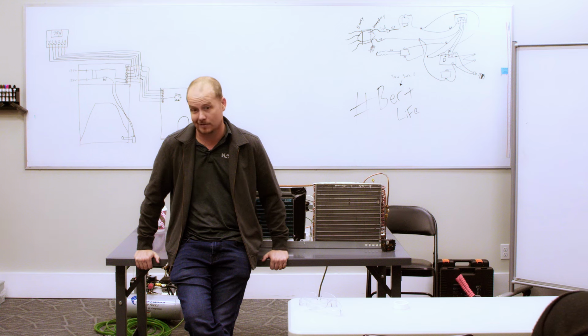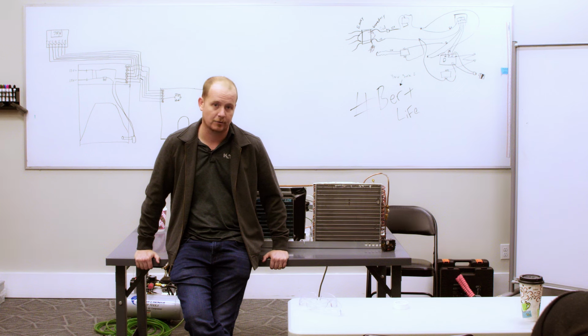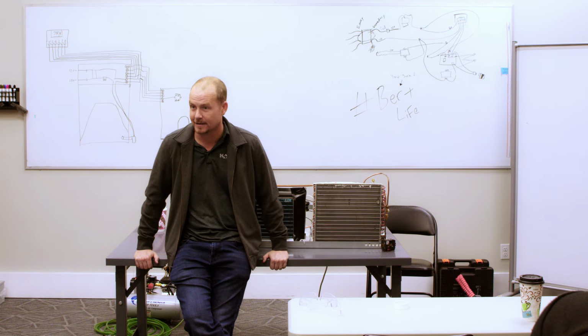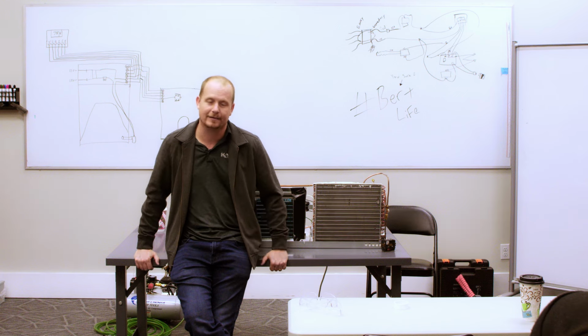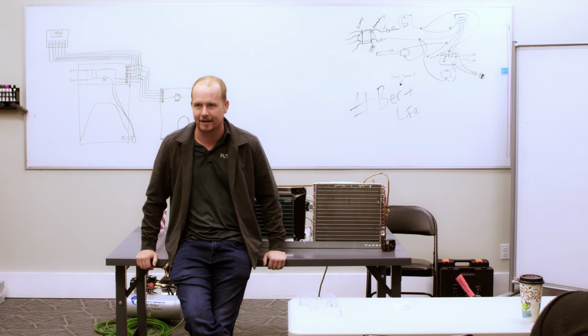And even easier than that, it's almost always around 10. For most of the equipment we work on, other than microchannel condensers, it's so close to 10 that you can pretty much just guess it's 10 in most cases. It may be 8, it may be 14. I'm not telling you not to follow what the data tag says, but I'm just saying that it's always close to 10.